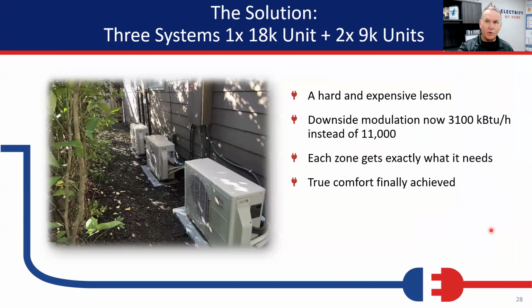We took out the multi-zone and put 3 individual single zones out there. The modulation rate on these smalls is 3,100 per zone. So I can do 3,100 in that bedroom zone instead of maxing it out at 9. And this is an expensive lesson if you think about it. I'm sure it took a little while to sell that other 3 zone. I don't remember the disposition on that, but these units we had to go out and buy 3 outdoor units and then redo the wiring and do all this work to actually fix this problem.